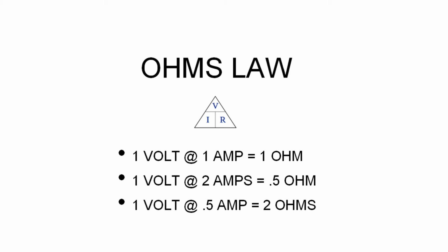This is critical later as we calculate the voltage drop between our photovoltaic panels and the house, going through copper wires usually. We need to be able to prove to the inspector that there won't be enough resistance and voltage drop to make the system not work. The inverters, the battery chargers, and so on just won't work if we have the voltage out there at the panels, run through these wires, and the thing doesn't work. There was too much of a drop because we didn't have the right size copper wires. So that, in essence, is what Ohm's Law is about.